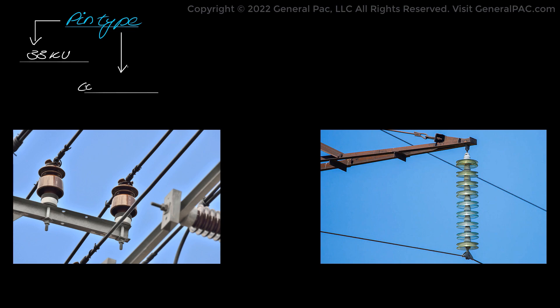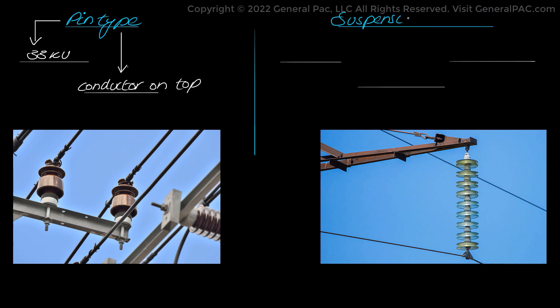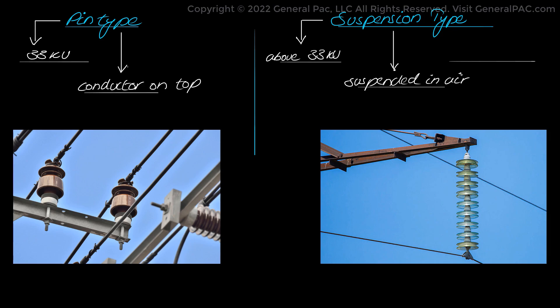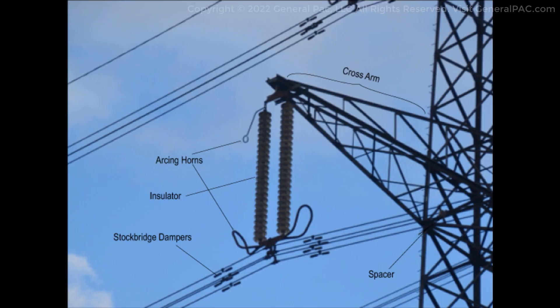Pin type insulators carry the conductors on their top and have structures consisting of sheds or petticoats, which prevent insulation leakage. Suspension type insulators are suspended and clamp the conductors from below. They consist of discs of porcelain, and up to 19 discs may be used for 400 kV lines. Cross arms are arms protruding from the tower to carry the conductor at a certain distance apart, and the insulators are attached to the edge of these cross arms.